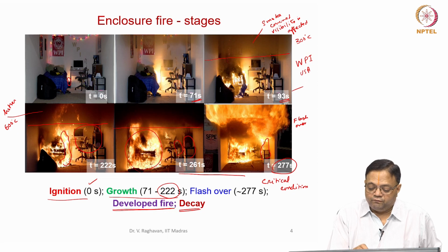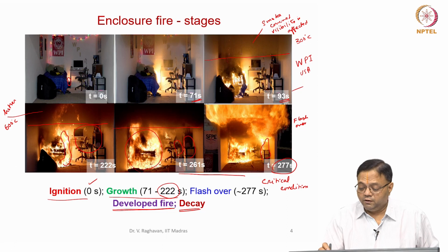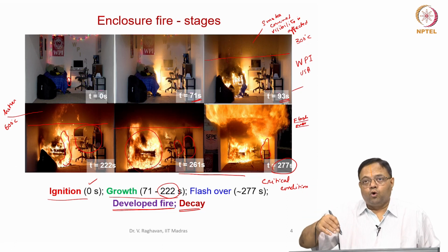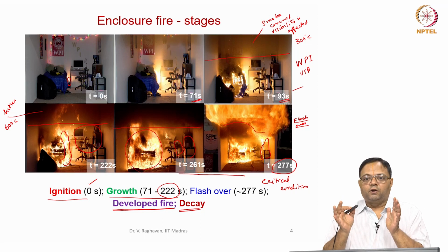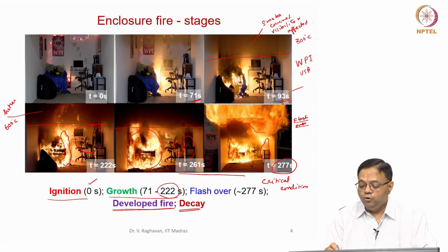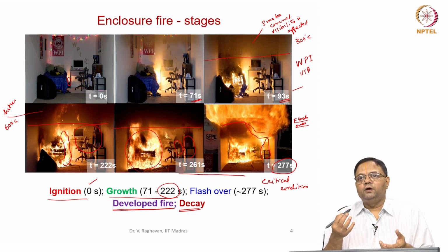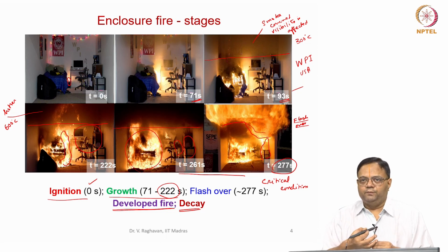Before flashover, only smoke comes out in this particular time period, but once flashover occurred, the heat release rate grows rapidly, so that you can see the fire itself comes out of the compartment. It is actually an open compartment, the front end is open, so maybe it's a door or something. So the entire fire comes out because of the very high intensity.